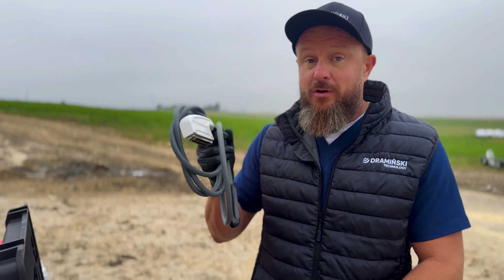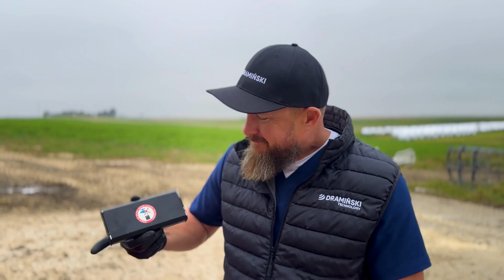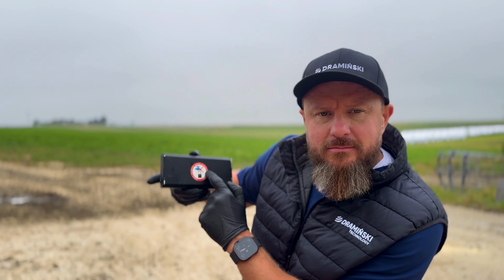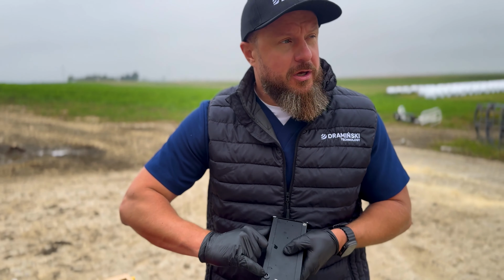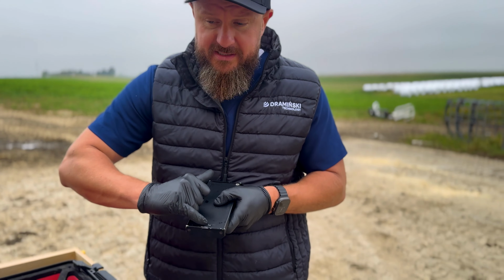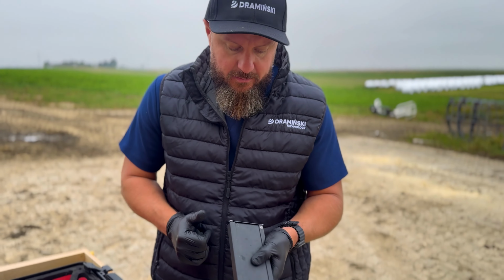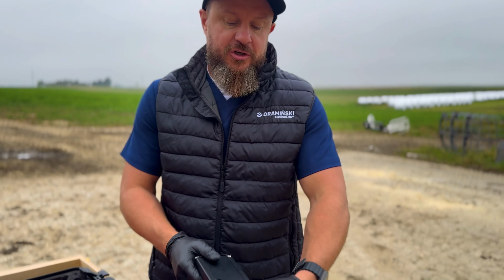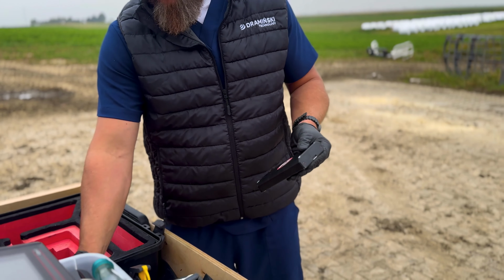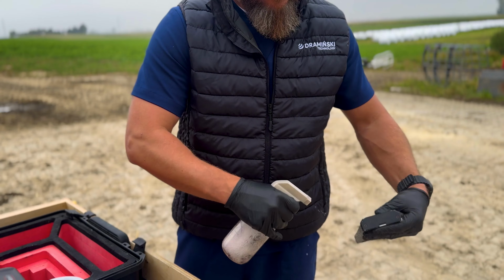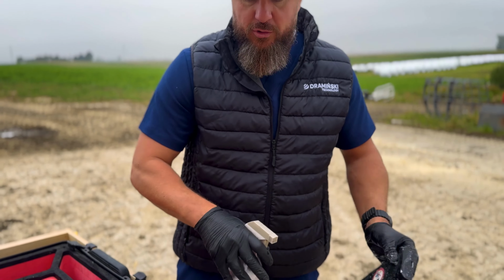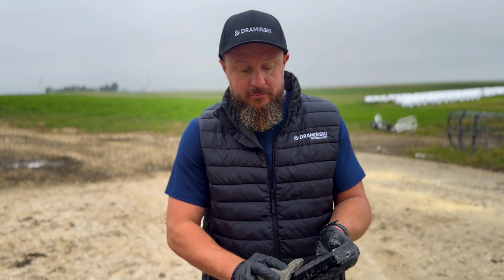The strap goes to the washing machine, and we still have 2 more elements: the probe and the battery. For the battery, each battery has a symbol showing it's not waterproof. We need to remember that. These parts, the charging port and the connection to the ultrasound, must not get wet. I usually cover them with my finger and spray the cleaning fluid onto the battery. Then I clean it with a sponge.